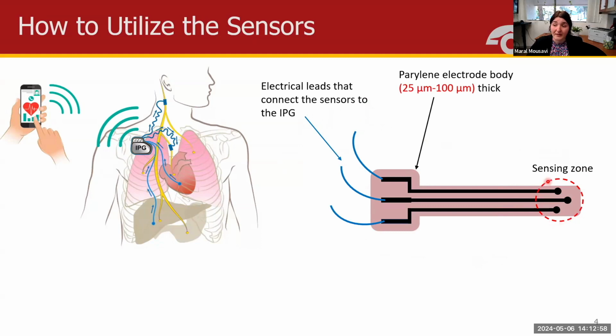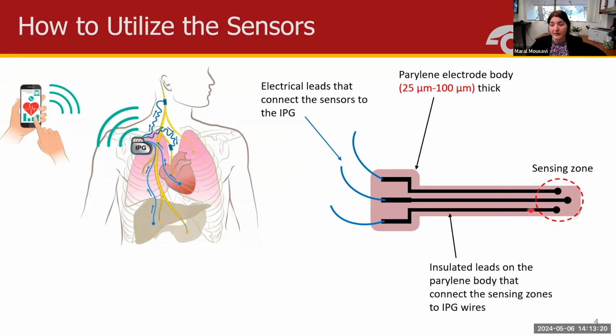Each electrode has an active sensing zone that needs to be in contact with the tissue. I'll talk about the size of these sensing zones, but this contains your electrode. This is a generic design for what a sensor could look like, and we're customizing the designs based on the actual clinical indication, as well as the type of sensors that we're building. And then we have the leads that are insulated, so only the electrodes are actually electrically connected to the tissue for electrochemical sensing. And these leads take the signal back and forth to where we actually connect them to wires to the IPG.